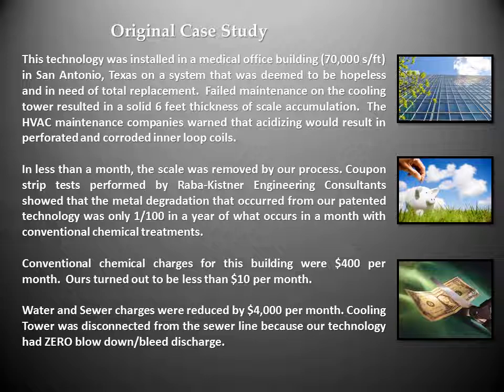Coupon strip tests performed by Raba-Kistner Engineering Consultants showed that the metal degradation that occurred from our proprietary technology was only 1/100th in a year of what occurs in a month with conventional chemical treatments, and a reduction in monthly chemical charges of more than 97%. Water and sewer charges were reduced by $4,000 per month, and the cooling tower was disconnected from the sewer line because our technology had zero blowdown and bleed discharge.